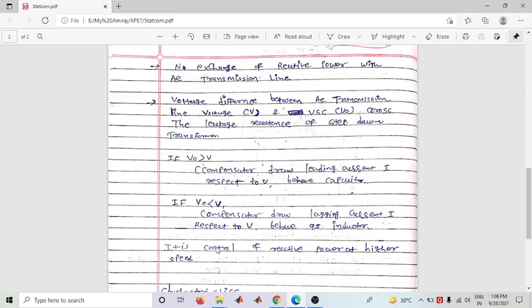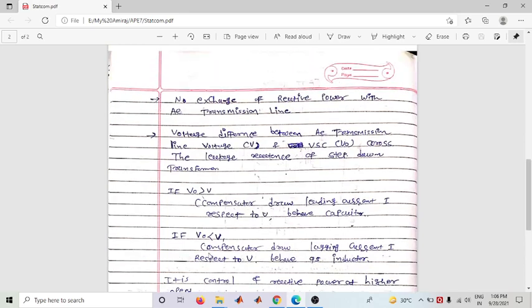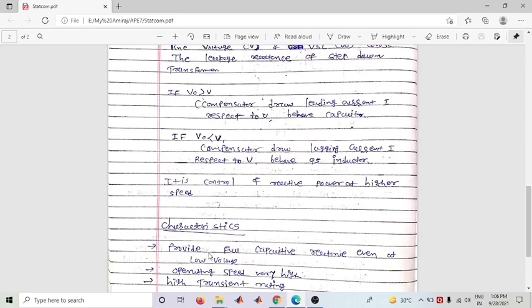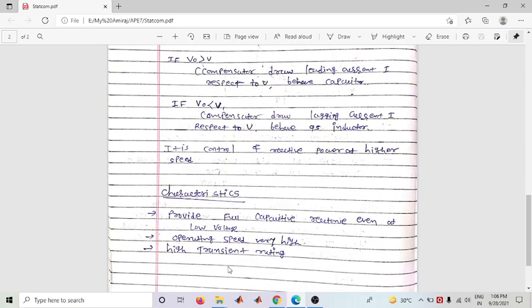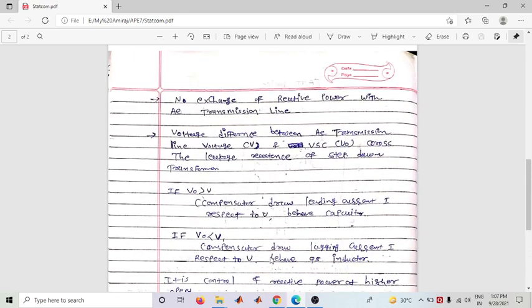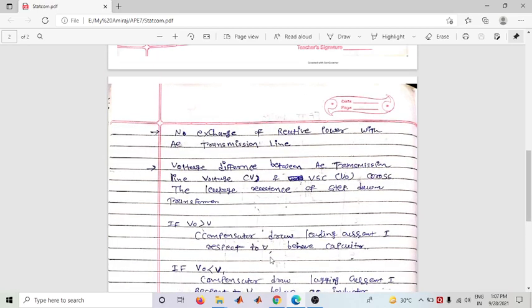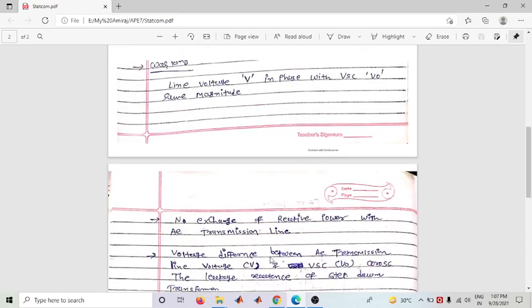STATCOM can control reactive power at very high speed in both conditions. Key characteristics include: full capacity reactive power compensation even at low voltage; very high operating speed; high transient rating. It operates in both lagging and leading power factor modes, keeping the power factor of the transmission line under control.